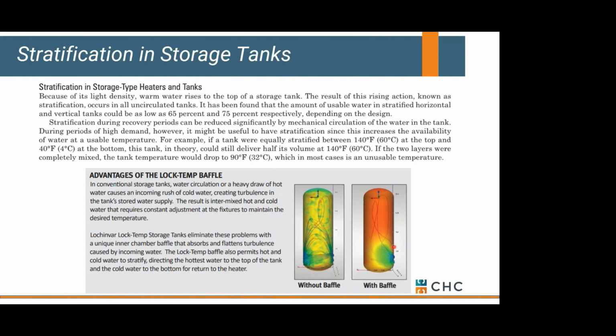So yeah, it really depends on what tank you're utilizing. The other thing is if you lay the tank on its side, it becomes horizontal. That's fine too, but your stratification or your drawdown becomes about 65 to 75%. Okay, it's not as great as it is in a vertical tank.